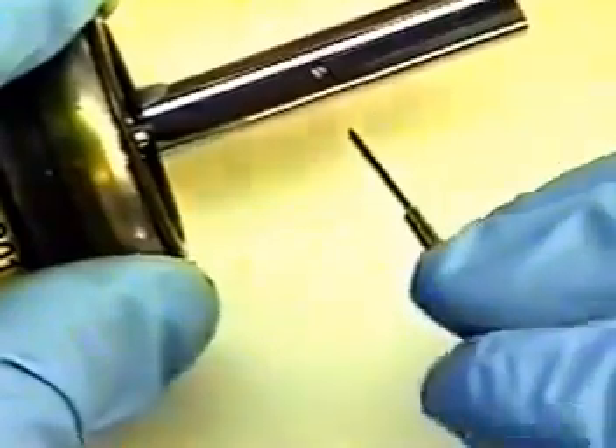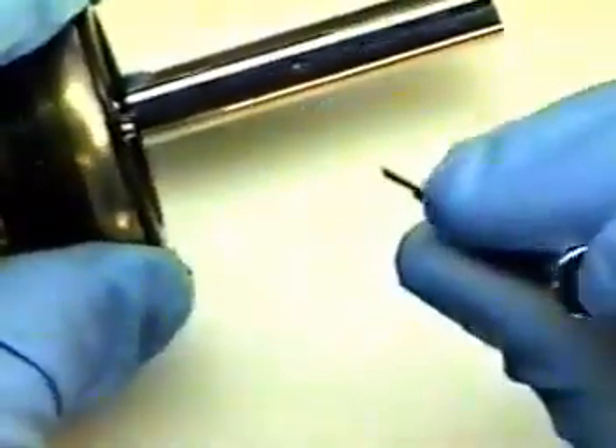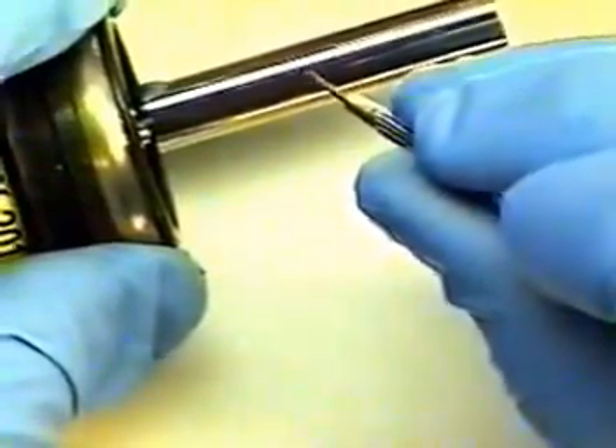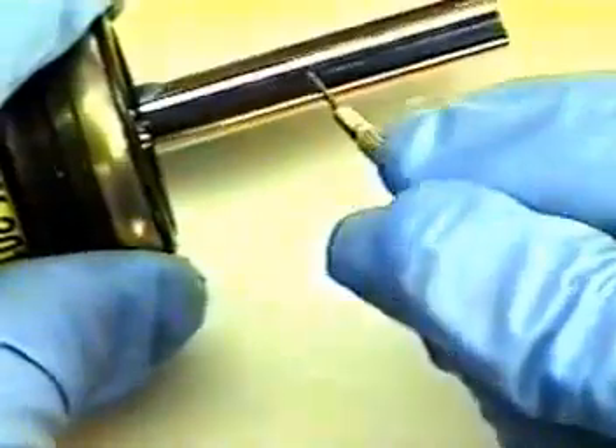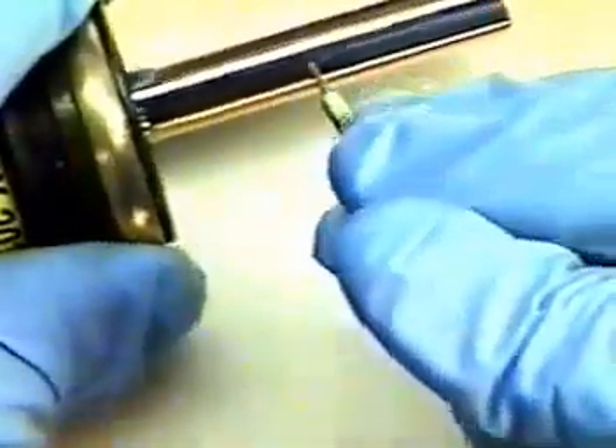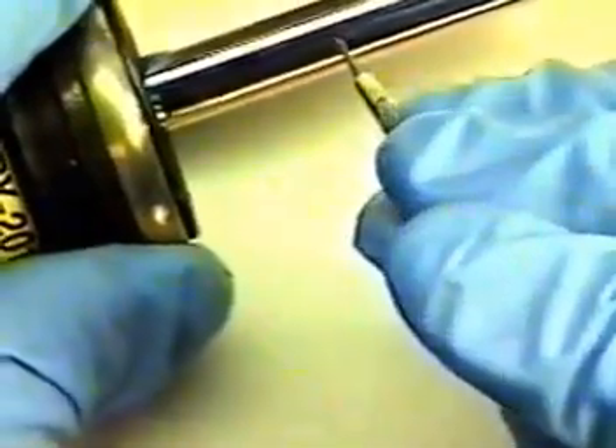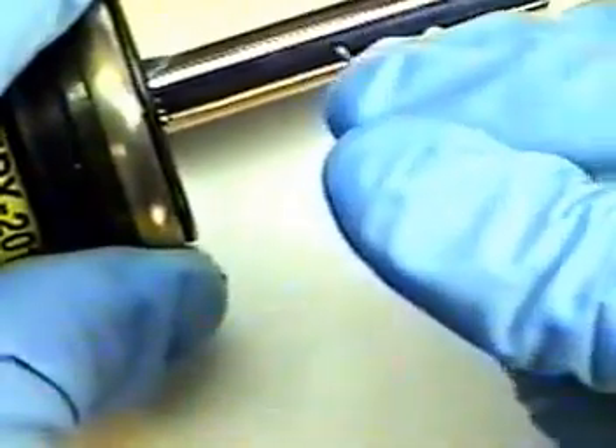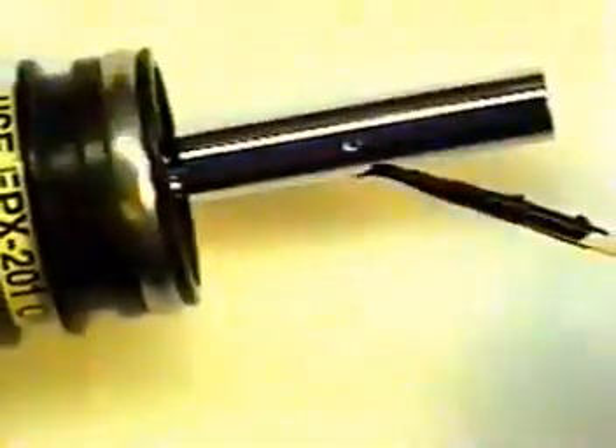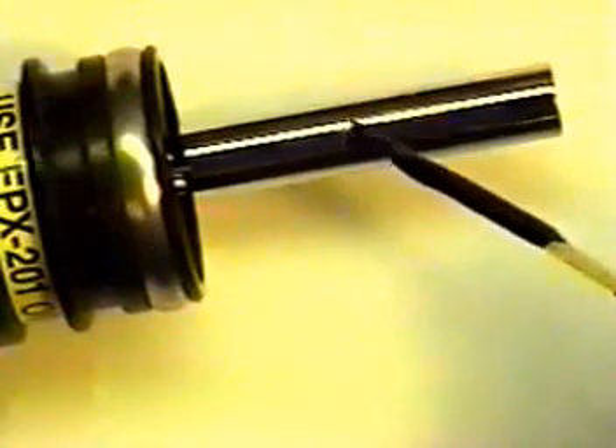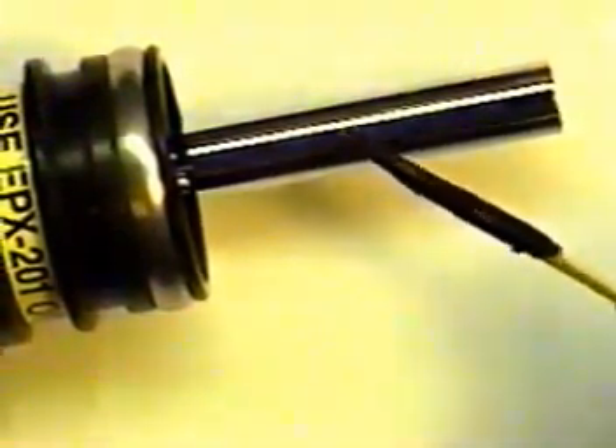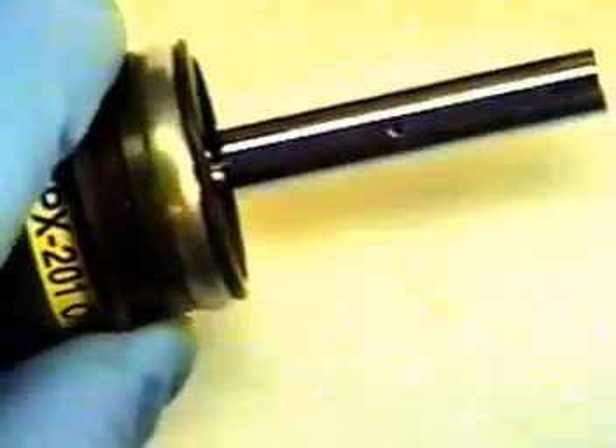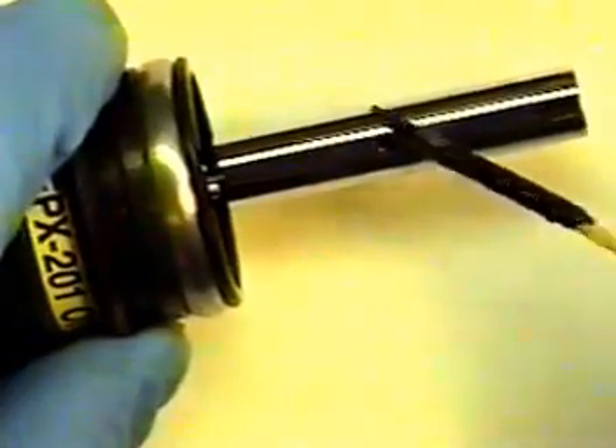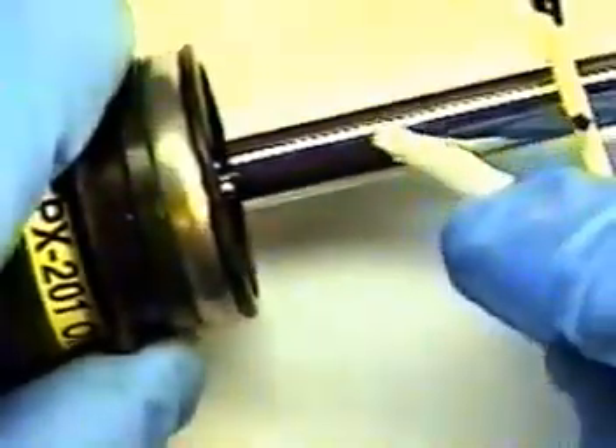Find your set screw on the light guide probe and using a small number 1 screwdriver, tighten down your set screw. This holds the light guide in place. Do not over tighten, just finger tighten. Otherwise you can cause damage to the light guide probe. Using some black RTV, fill the hole so as to cover the top of the set screw. Be sure to fill the hole completely. This will allow for a watertight seal. Wipe off any excess. Allow this to dry.